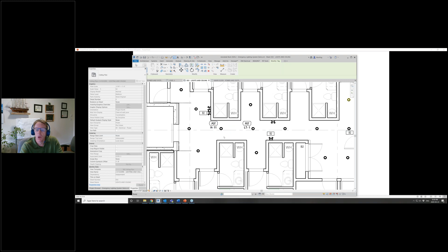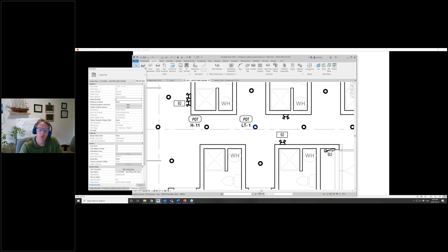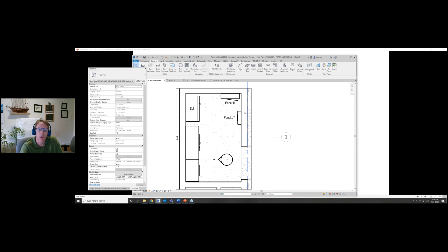So this guy is now on panel LT1, which is powered through the emergency lighting inverter. And this light next to it is on the house panel. So these two pot lights will respond a bit differently in case of a power outage. This pot light will go out because it's on the house panel. This one will stay on because it's on panel LT, which is served by way of the emergency lighting inverter. So panel H serves panel ELI, serves panel LT, which then in turn serves our backup lighting.